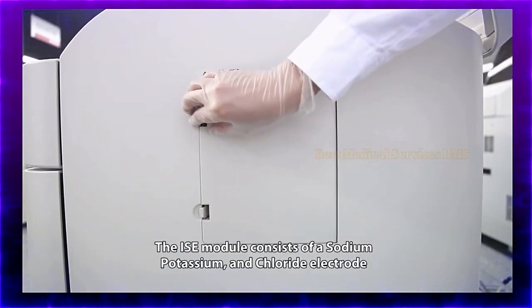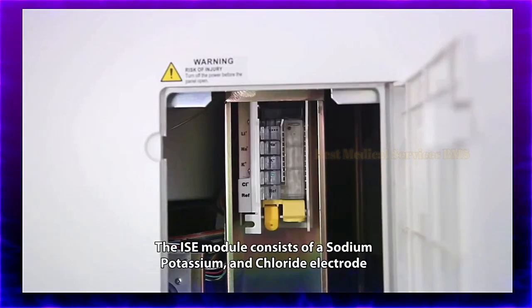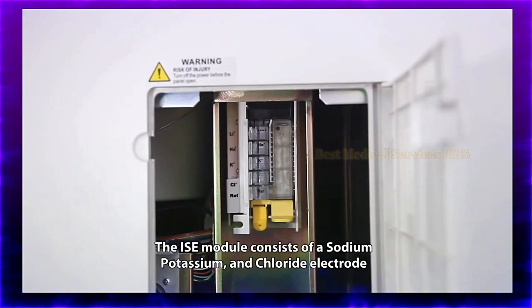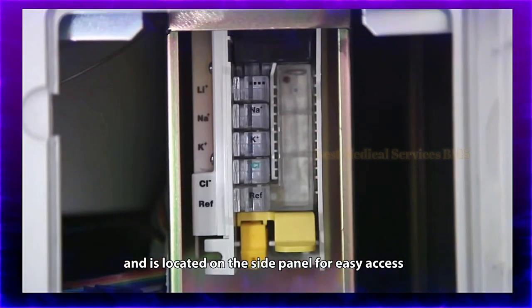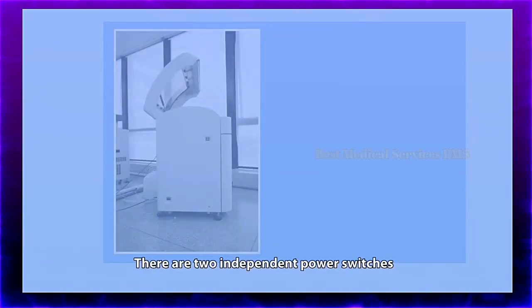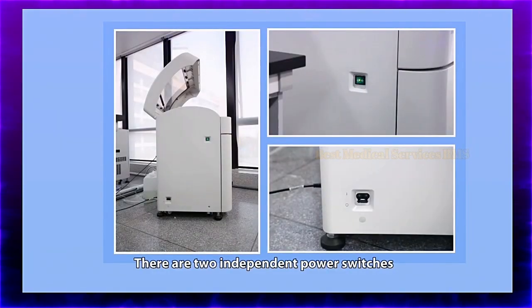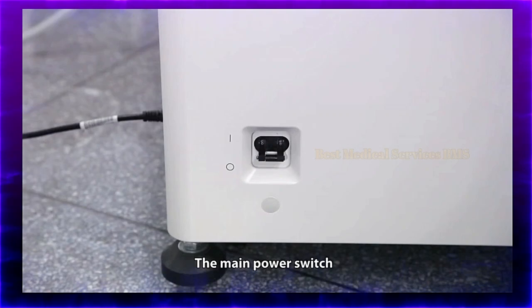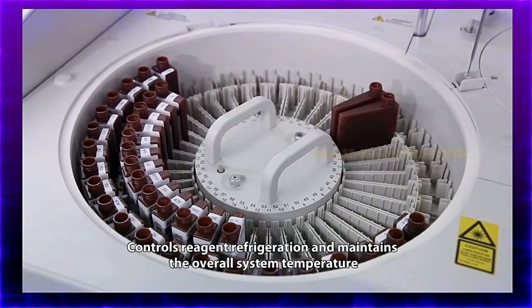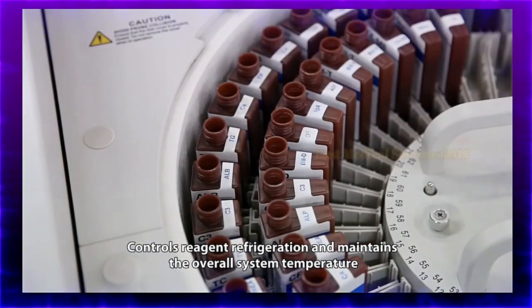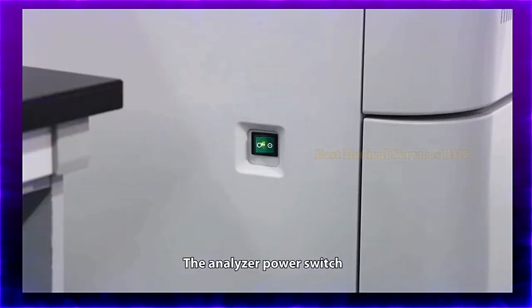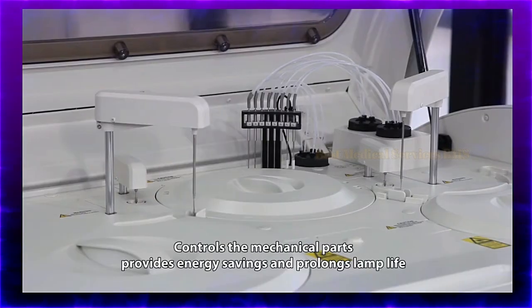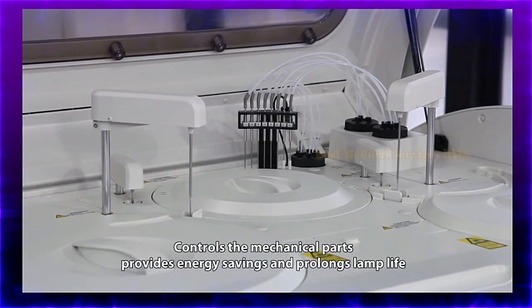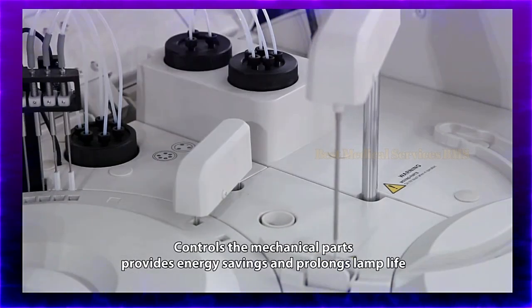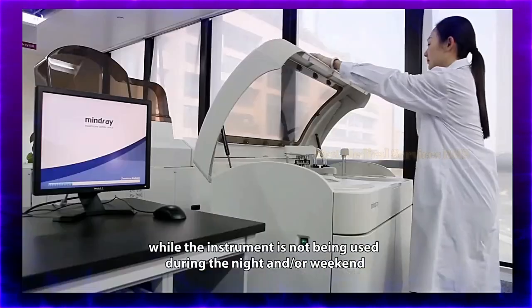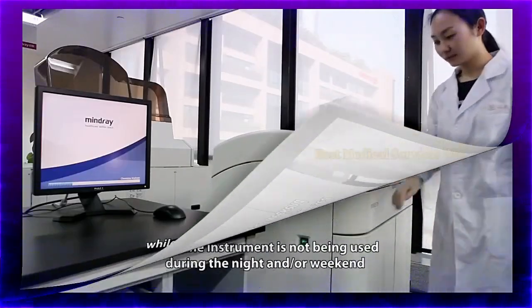The ISE module consists of a sodium, potassium, and chloride electrode and is located on the side panel for easy access. There are 2 independent power switches. The main power switch controls reagent refrigeration and maintains the overall system temperature. The analyzer power switch controls the mechanical parts, provides energy savings, and prolongs lamp life while the instrument is not being used during the night and/or weekend.